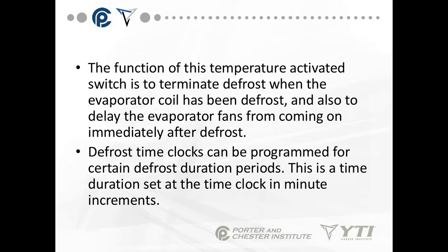The function of this control is to terminate defrost when the evaporator coil has been defrosted, and also to delay the evaporator fans from coming on immediately after defrost. Because once you have a warm coil, you also have moisture. You don't want to blow that moisture around the space you're trying to cool, especially in a deep freeze, because that moisture will create frost and almost like snow all over the place. You want that moisture to refreeze on the coil after some of it has drained away.